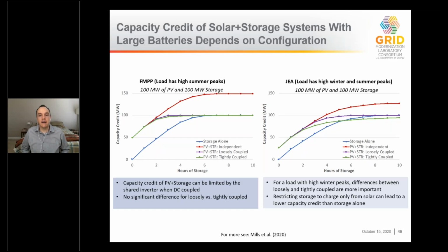If you start to bring these things together with any shared infrastructure, like a shared inverter or a shared point of interconnection limit, as in these green and purple lines, one thing that can happen is that your solar could be discharging at the same time as your storage, effectively capping the total capacity credit of that solar and storage asset. So it's important to keep in mind that limitations like that can impose a constraint limiting the flexibility of the storage you're able to get out of it. You want to be cognizant of that and design the system accordingly.